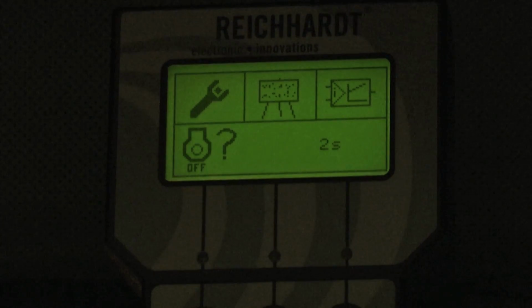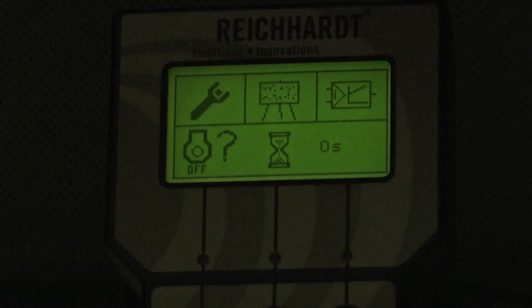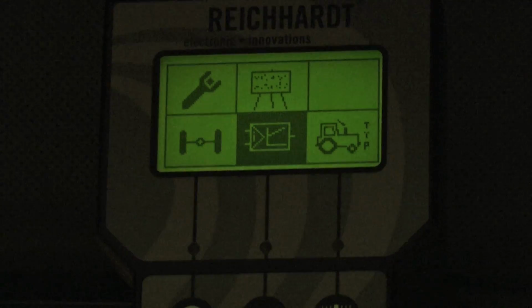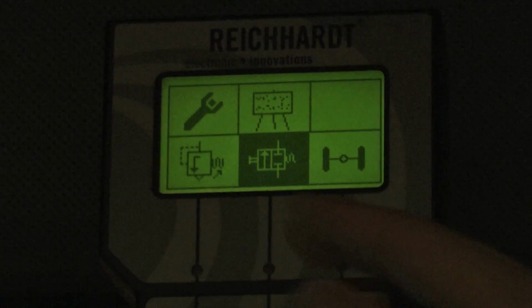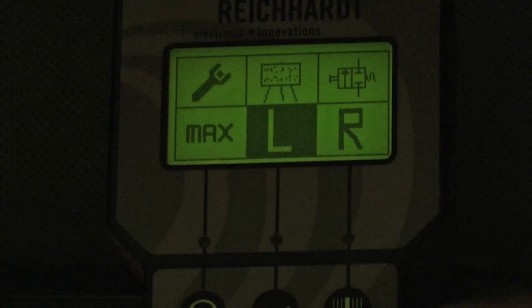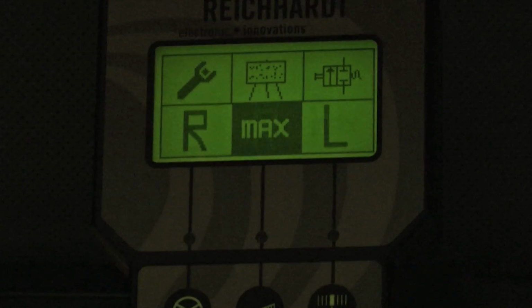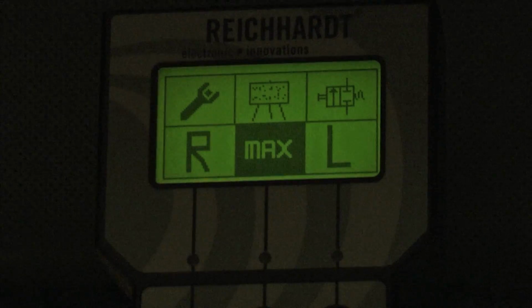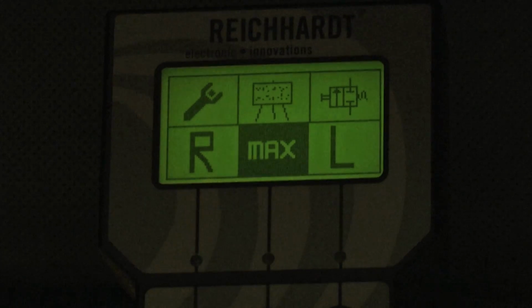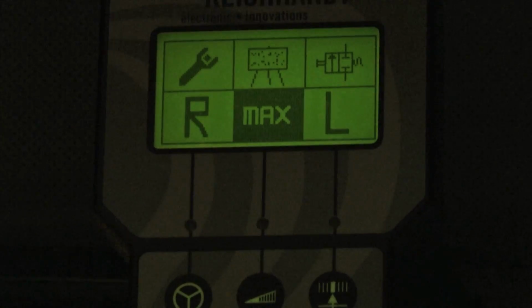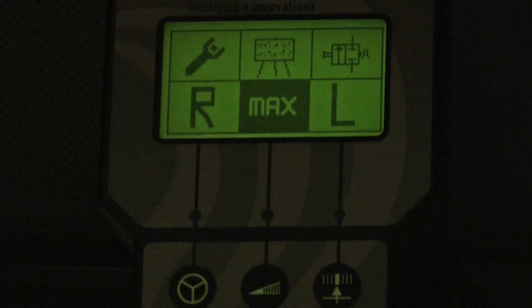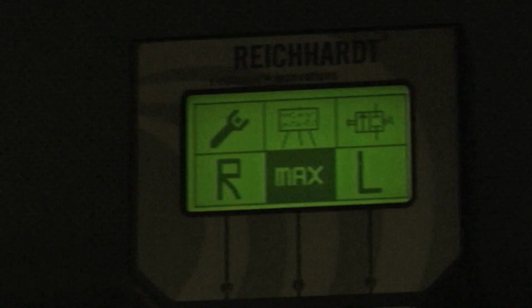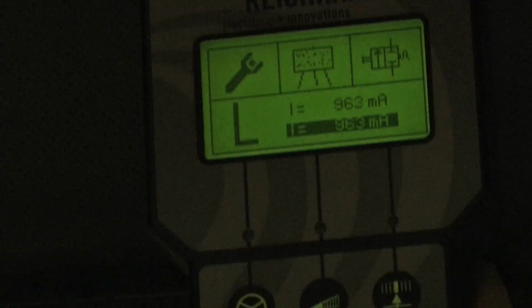Okay. The other valve calibration looks like a hydraulic valve. Go into this icon. You have left, right, and max. Left and right are the min, we call them crack points for left and right steering. And then the max, as we discussed earlier, is the maximum setting for either left or right outputs. Default's going to be 500. The minute I go into this left icon, it's going to send current to the left output. And right now it's sending 963 milliamps, for example.